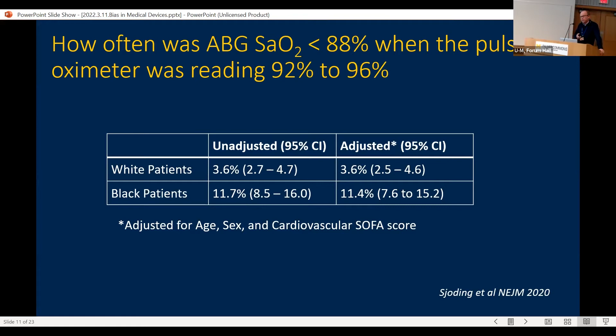We also did a few other analyses just to confirm that these findings are robust and hold true. So we looked at the pulse oximeter's ability to detect a low oxygen level of less than 88%, which everyone would consider problematically low. And it turns out in Black patients, the area under the receiver operating characteristic curve to detect this level of oxygen was 0.84. Whereas in white patients, it was 0.89. Not a huge difference, but think about how common the pulse oximeter is, how often it's being used across hospitals all over the world. Small differences can really add up.